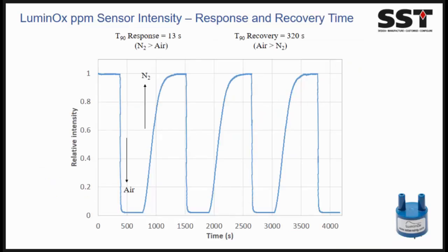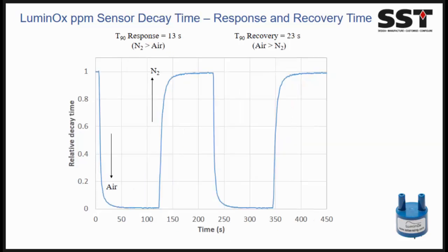Another important factor is the response time, as you can imagine. Again, this is another disadvantage of intensity-based sensors. Here you can see that if you were to do an intensity-based sensor, the response time is particularly fast, but the recovery time is actually quite slow, about 320 seconds. The key thing here is that when you expose this ppm sensor to air, you get a nice repeatable and reversible signal. However, when we do decay time, you get a much faster recovery. So 23 seconds, and again it's nice and repeatable. This is what we call the true response time, and this is what we spec for a sensor.